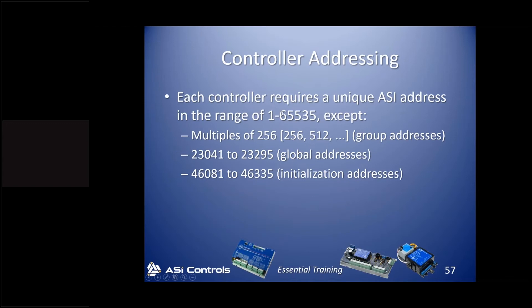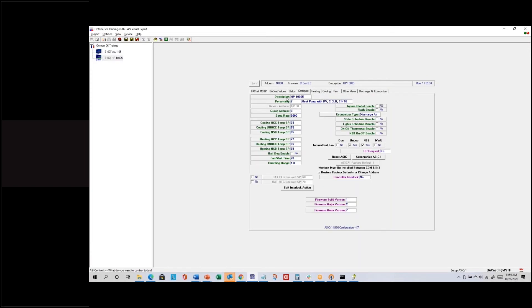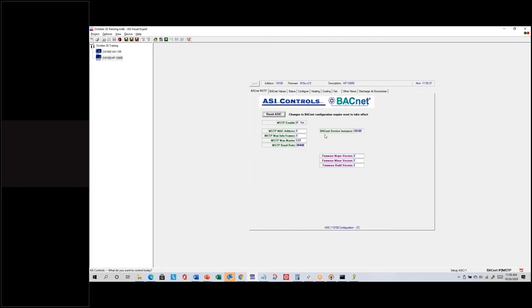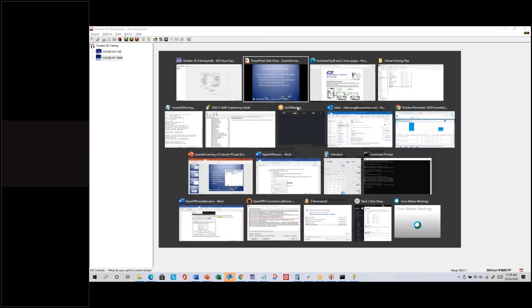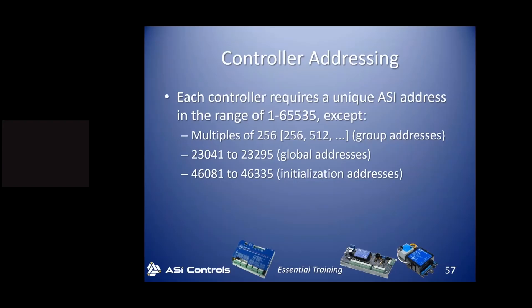Controller addressing — this is for the ASI address as opposed to the BACnet address. In ASI Expert, the ASI address is shown on the Configure tab as the device address, which is different from the BACnet address called the BACnet device instance. It's grayed out because there are only certain times you can actually change it. For the ASI address, you're limited to addresses between 1 and 65,000, with some exceptions: multiples of 256 are not allowed — those are reserved for group addresses used to change settings in a group of controllers with one command.